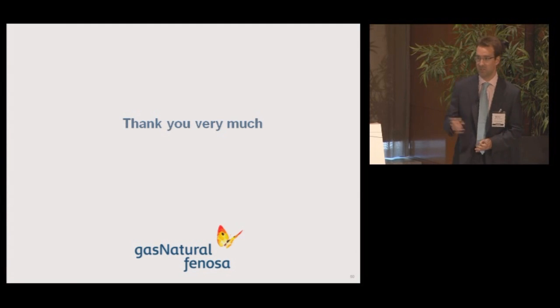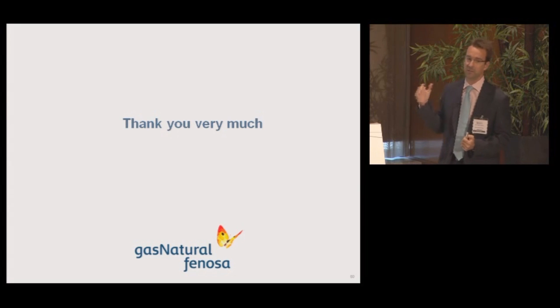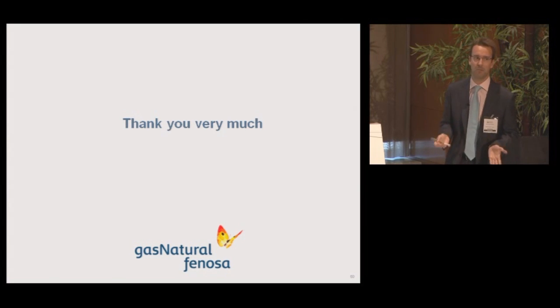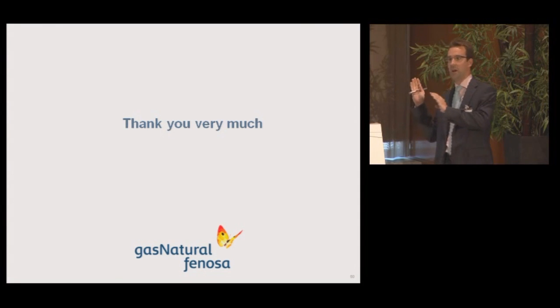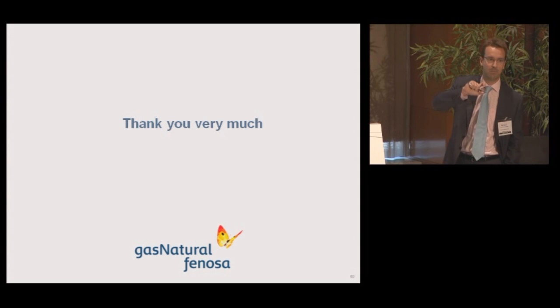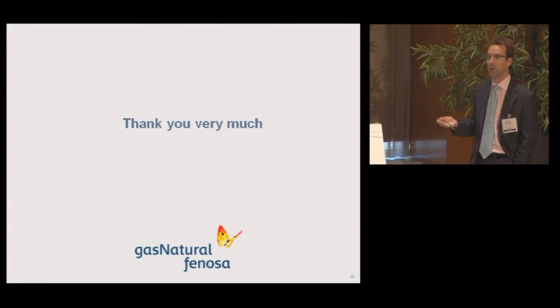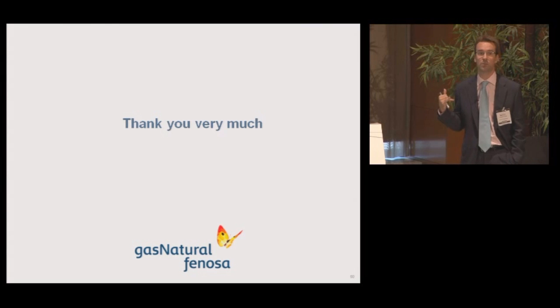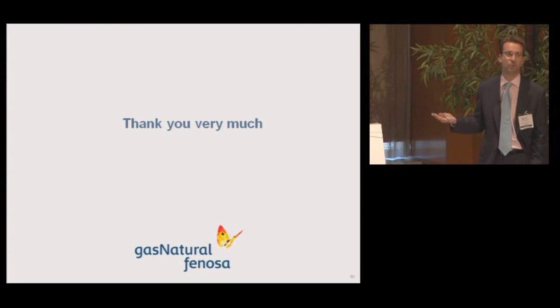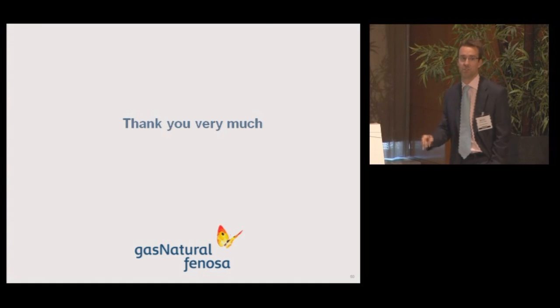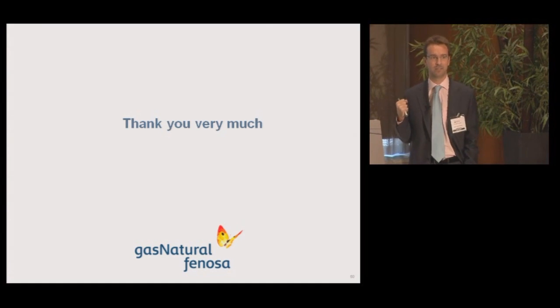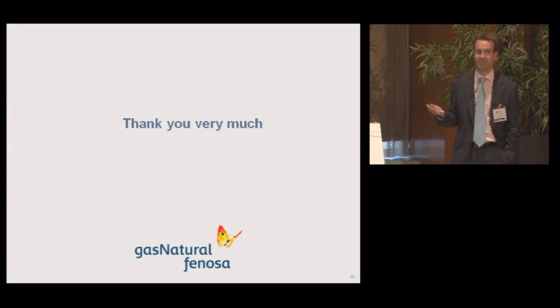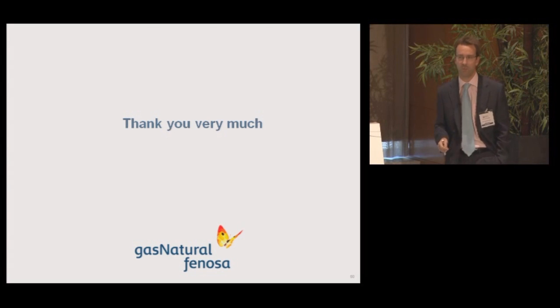Thank you, Antonio. This effect is very significant. Sometimes we've had problems because generators maintain a fixed power factor, and in the north part of Spain we've had problems with very high voltage because at 8 o'clock the scenario changes from valley to peak. Because of that, we have to call distributed generators and say, please don't do that. And they say, it's the law, I have to do this; if I don't, I'm not going to receive the incentive scheme, the money. So that's the issue — sometimes the regulatory framework is very important.